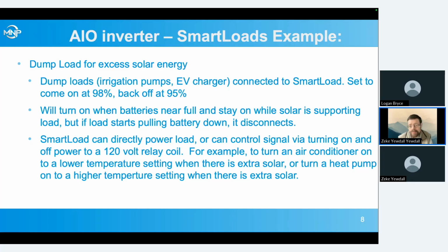This turns them on when the batteries get near full, and then as long as the solar is supporting that load, they'll just stay on. But as soon as the solar is unable to support that load and it starts pulling the battery state of charge down, it disconnects. We want to put a little bit of room in between those two set points, just because we don't want things turning on and off too rapidly.